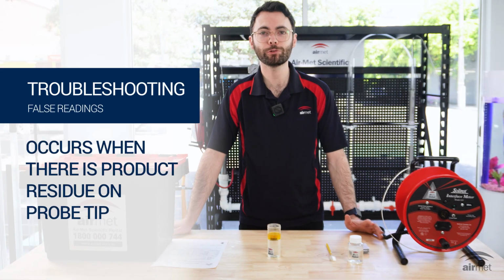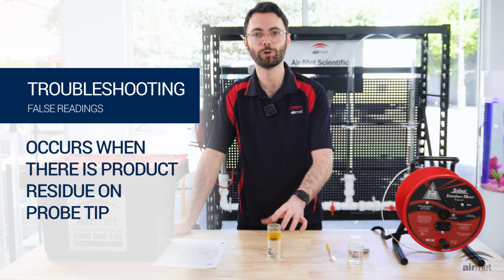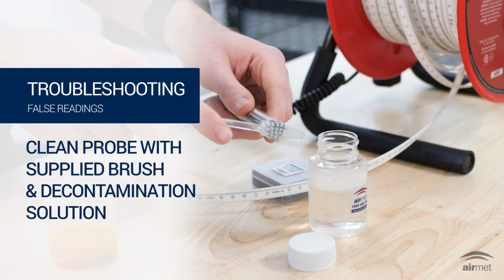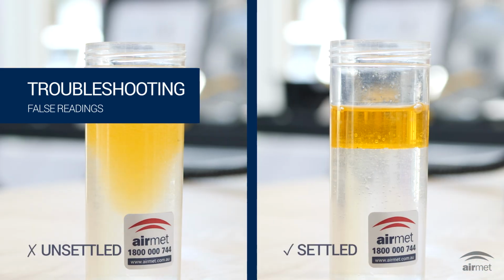False readings. False readings can occur when there is product residue on the probe tip or when an emulsion starts to form on the product. Clean the probe carefully and wait for the emulsion to settle out of solution.